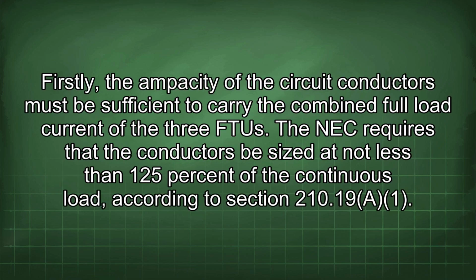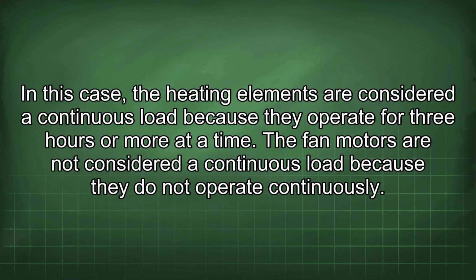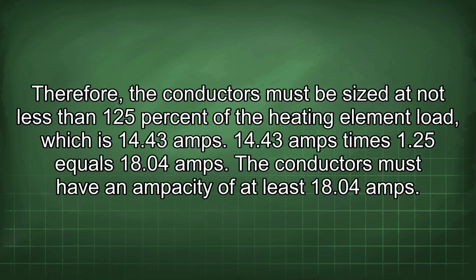Firstly, the ampacity of the circuit conductors must be sufficient to carry the combined full load current of the three FTU. The NEC requires that the conductors be sized at not less than 125% of the continuous load, according to Section 210.19(A). In this case, the heating elements are considered a continuous load because they operate for 3 hours or more at a time. The fan motors are not considered a continuous load because they do not operate continuously. Therefore, the conductors must be sized at not less than 125% of the heating element load, which is 14.43 amps.